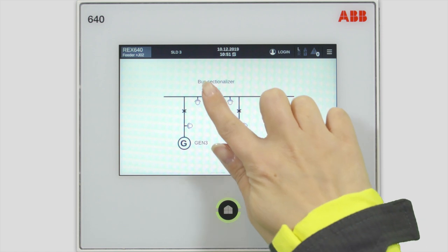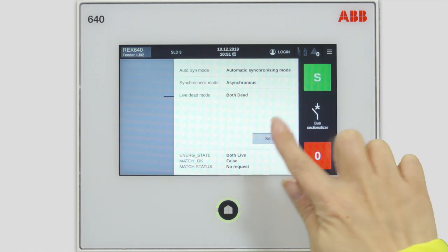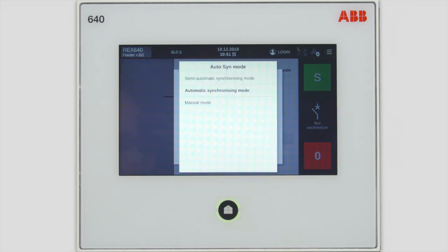Let's start the procedure by tapping the symbol of the breaker you want to close. Different options to do synchronization are shown under the settings. In manual mode, all controls must be done manually, including closing of the breaker. In semi-automatic mode, the relay takes care of the controls, but the breaker closing has to be done manually. In automatic mode, all will be handled by the relay. Let's stick with the automatic mode.